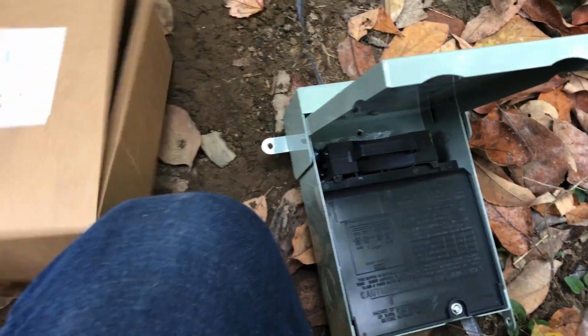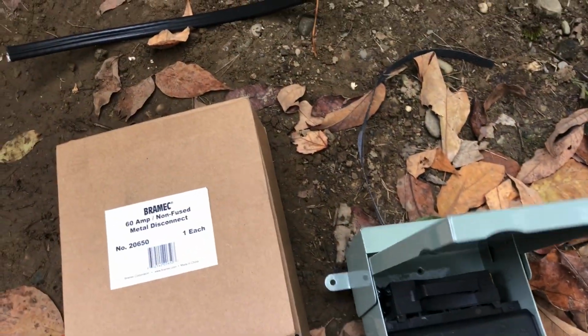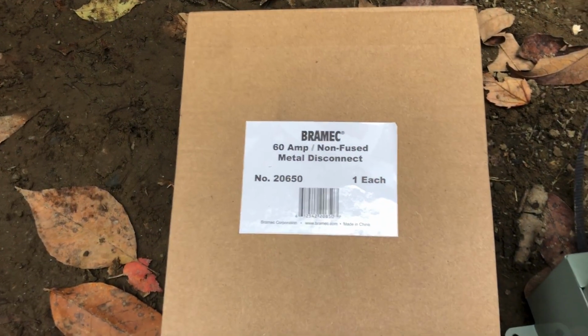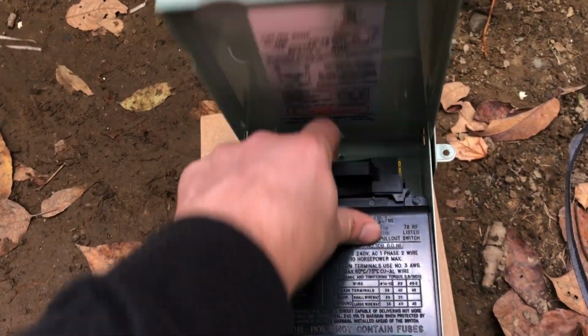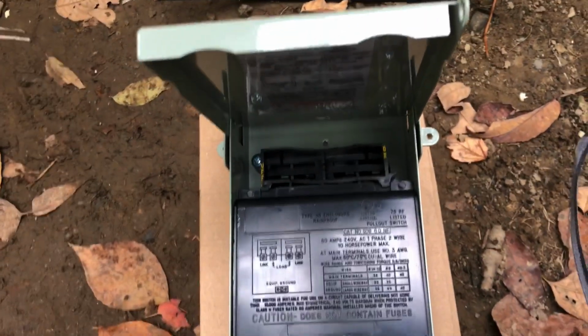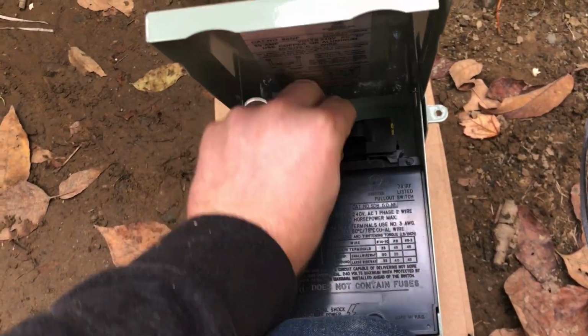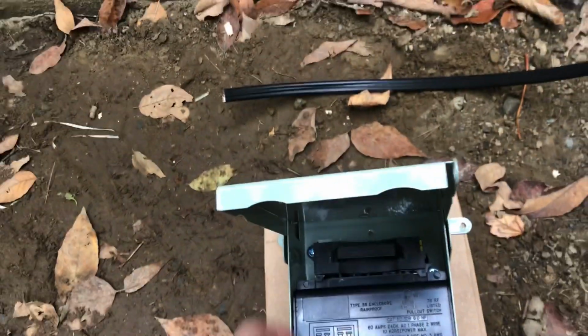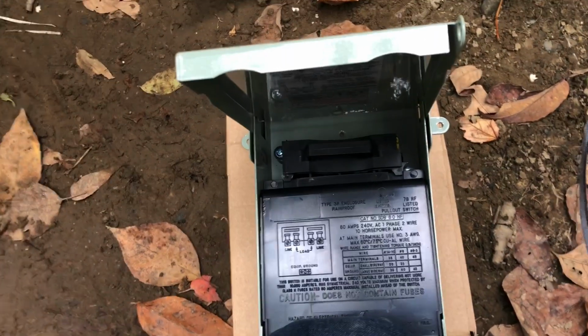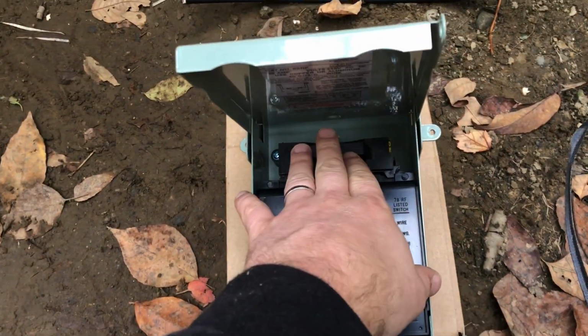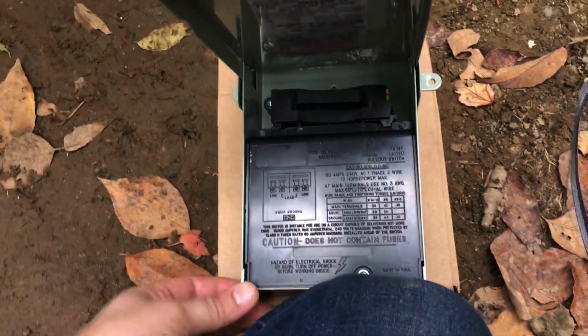Next thing you're going to need is this, which is a disconnect box. Don't worry about the fact that it says 60 amp. It means it's up to 60 amp. This doesn't have any breakers in it. Literally the only job is to disconnect the power by doing that. And this is made so that if you ever needed to service the unit, or in case of an emergency, you'd be able to pull this and disconnect all the power to the unit.